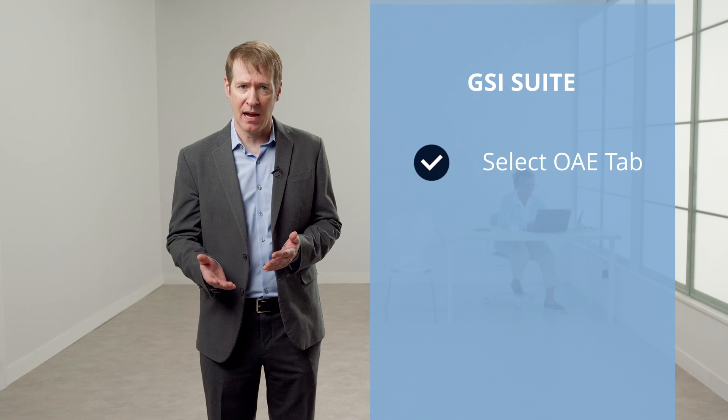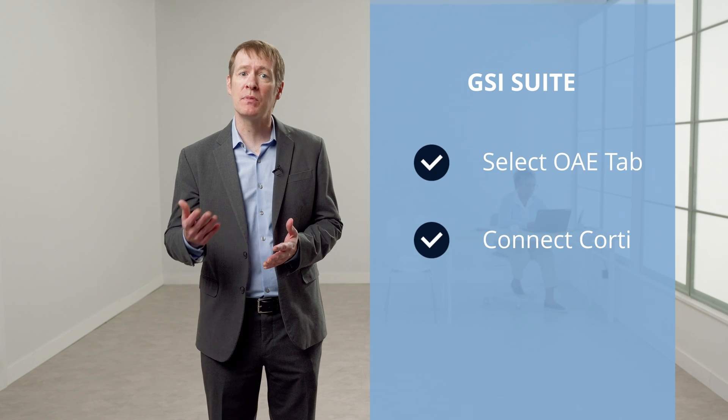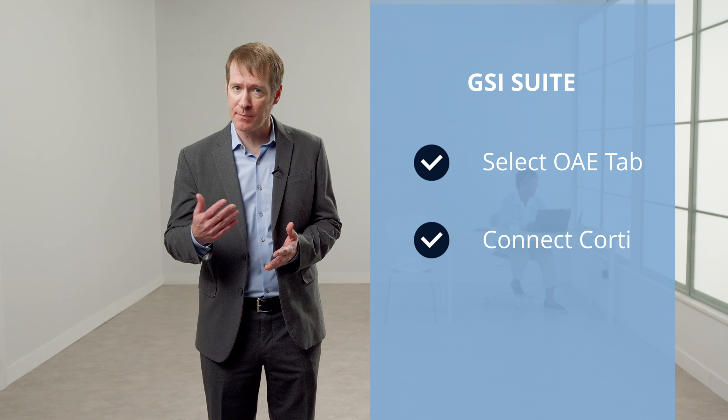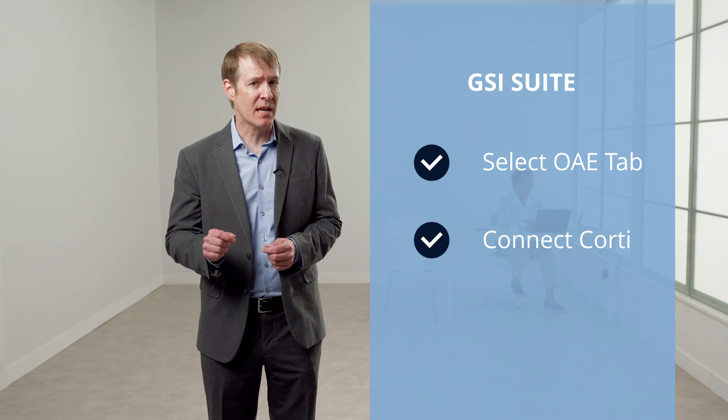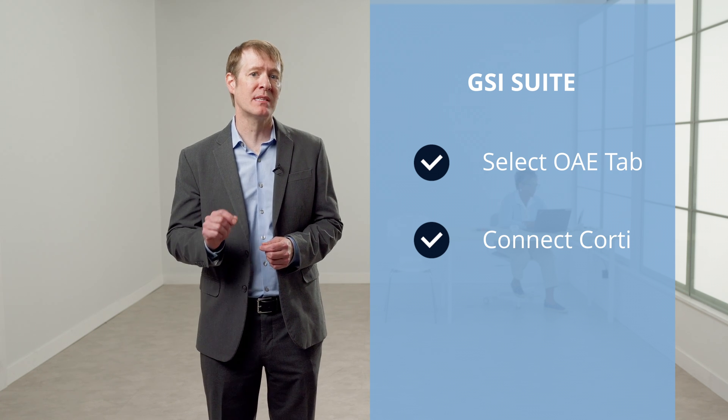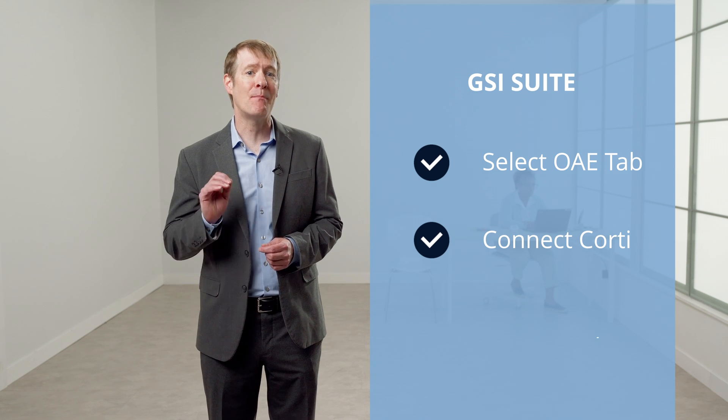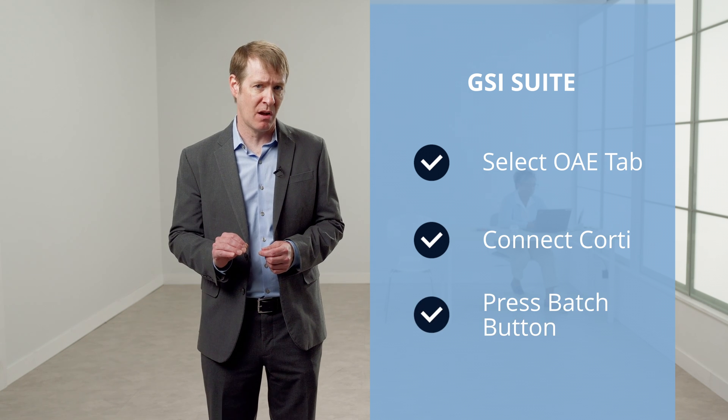GSI Suite allows for combining OAE test results with audiometric test data. To transfer data to GSI Suite, select the OAE tab, connect the Corti to the computer with a micro USB cable or by using the optional cradle, ensure that the power is on and when the display screen says 'waiting on PC', press the batch button on the GSI Suite software. This will transfer all of the test results saved in the Corti and place them into an assigned tests window, from which you may drag and drop the results into the appropriate patient record.